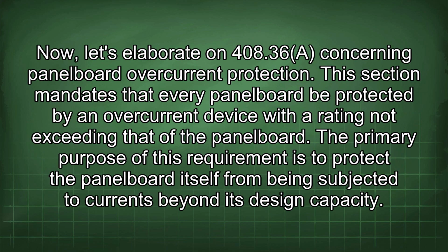Now, let's elaborate on 408.36 concerning panel board overcurrent protection. This section mandates that every panel board be protected by an overcurrent device with a rating not exceeding that of the panel board. The primary purpose of this requirement is to protect the panel board itself from being subjected to currents beyond its design capacity.